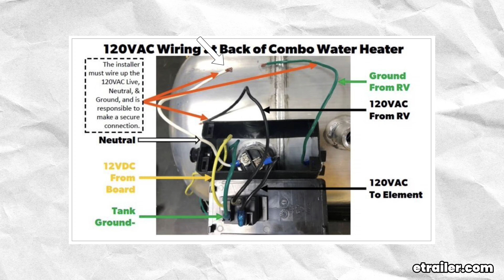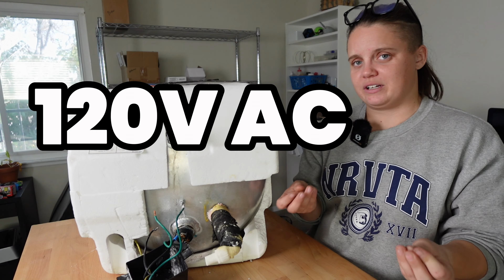So the next thing we're going to test is the AC in, because that's the next easiest thing to test. You'll see 3 wires coming into this box: a black, a white, and a green wire. With power on, put your red probe into the black wire nut and your black probe into the white wire nut—a little counterintuitive there. You should see a reading in the realm of 120 volts AC.